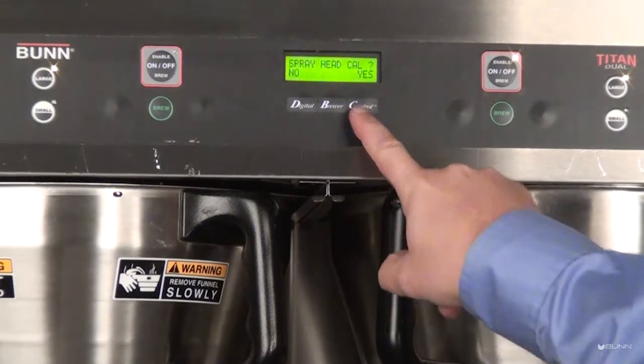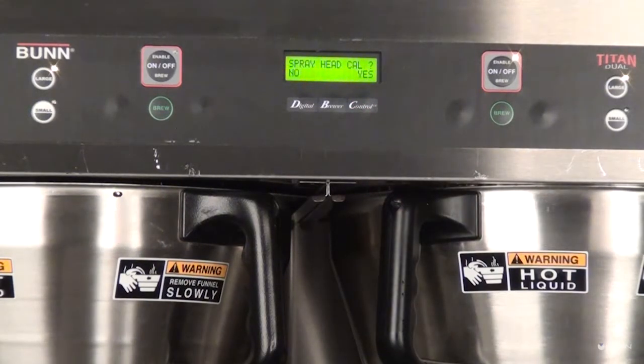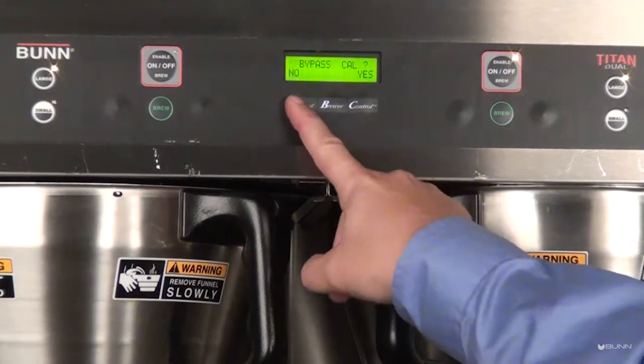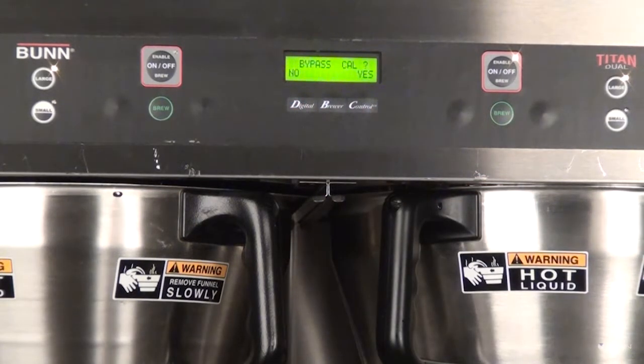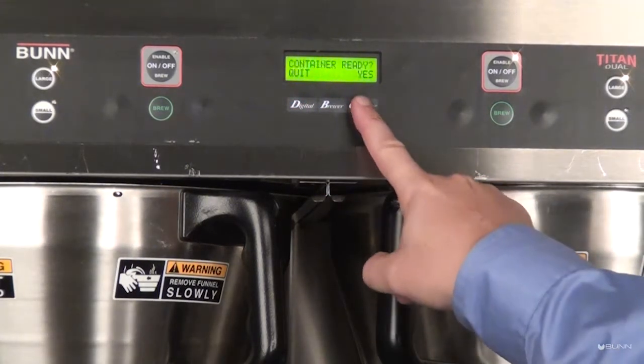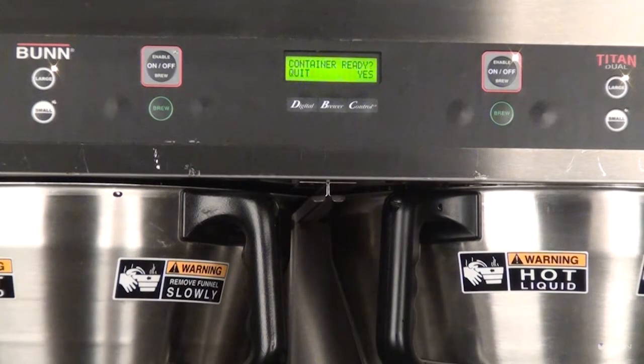Select Yes with the control switch. The display screen will now read Spray Head Cal. Select No to advance to the bypass calibration option. The display screen should read Bypass Cal. Select Yes to accept the bypass calibration.